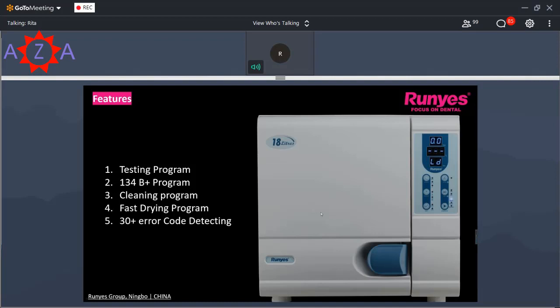And the next is the 134-degree B+ program. This program is very useful for the implantologist. In this cycle, the autoclave remains at 134 degrees for a sterilization time of 18 minutes. So cotton swabs and hollow equipment give better results in this.